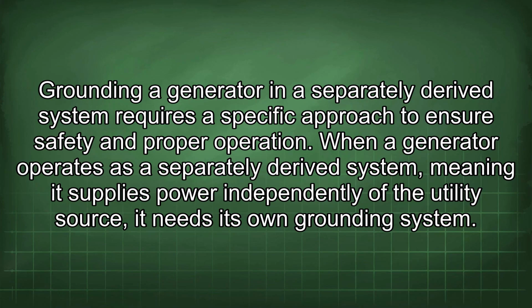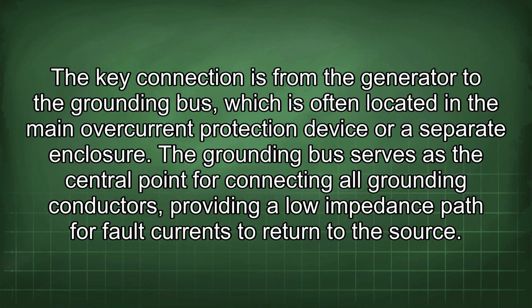Grounding a generator in a separately derived system requires a specific approach to ensure safety and proper operation. When a generator operates as a separately derived system, meaning it supplies power independently of the utility source, it needs its own grounding system. The key connection is from the generator to the grounding bus, which is often located in the main overcurrent protection device or a separate enclosure. The grounding bus serves as the central point for connecting all grounding conductors, providing a low impedance path for fault currents to return to the source.